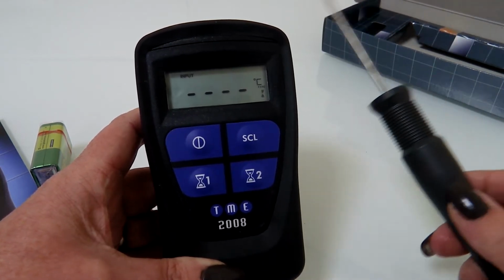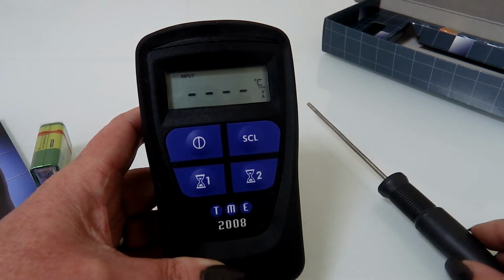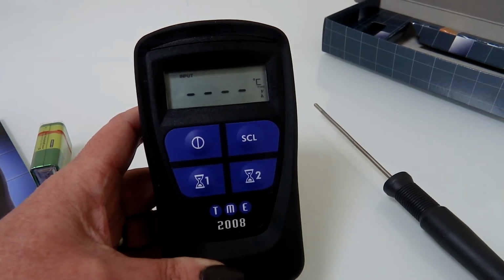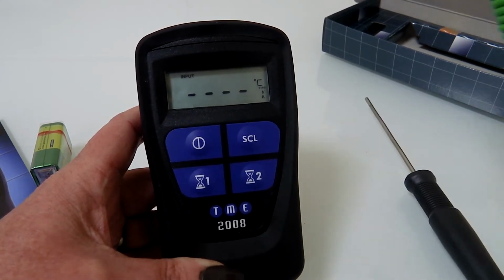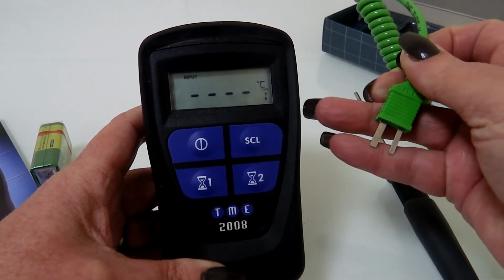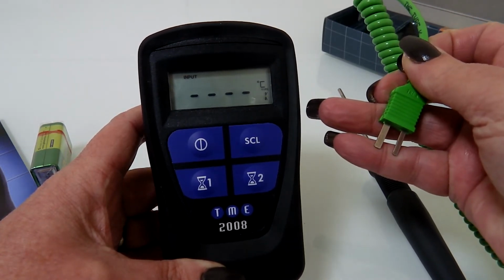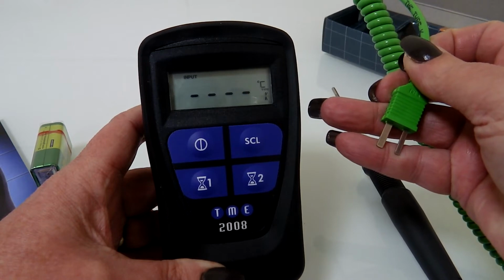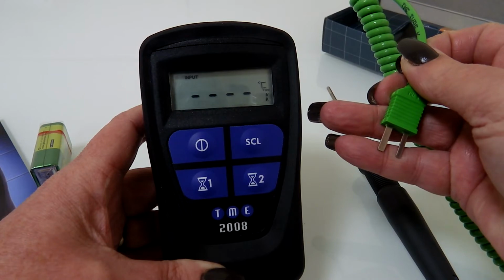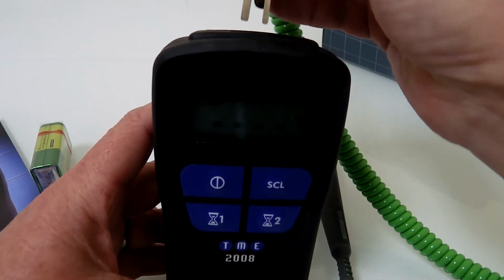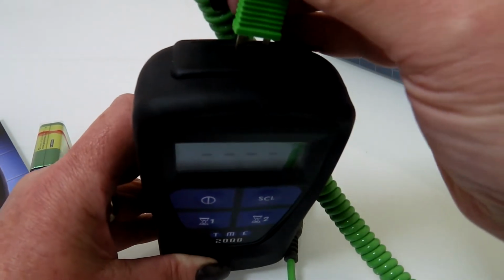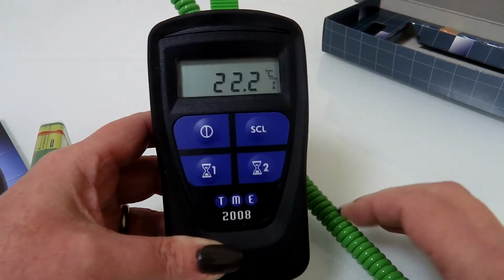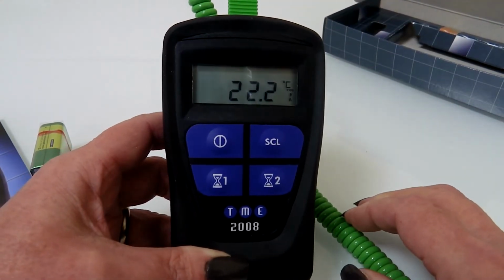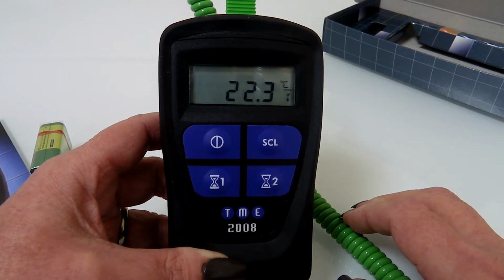Okay, so to get rid of those lines, let's insert a probe. For this video, I'm using our standard immersion probe, the KM03. Taking a look at the plug, you'll see the pins are two different sizes, the one on the right being slimmer. It's important that when plugging your probe into the MM2008, these pins are inserted the correct way round. In this case, with the display facing us, the slimmer pin stays on the right. If you force the pins in the wrong way, your reading will go backwards.